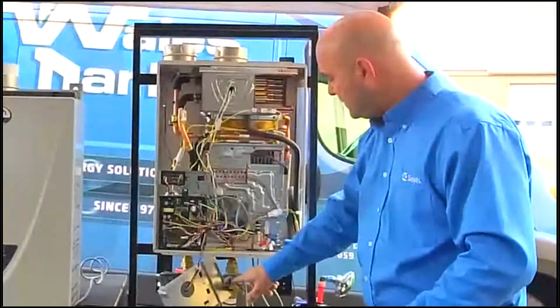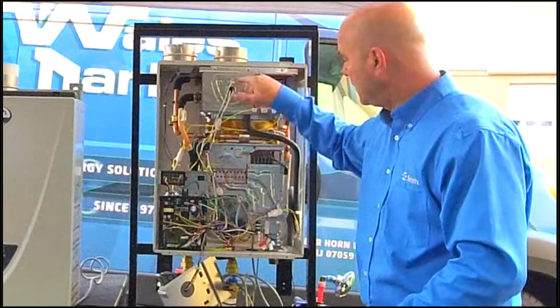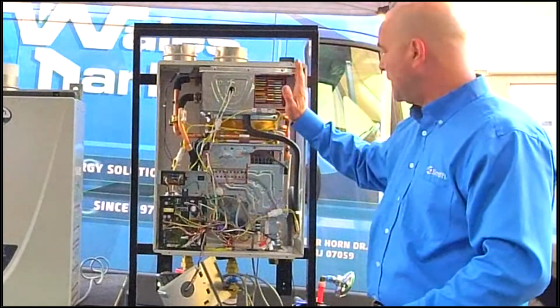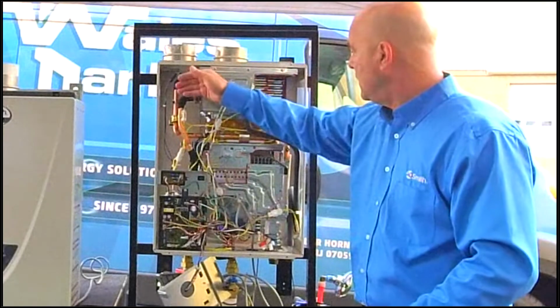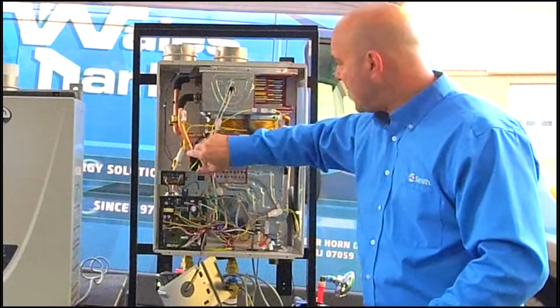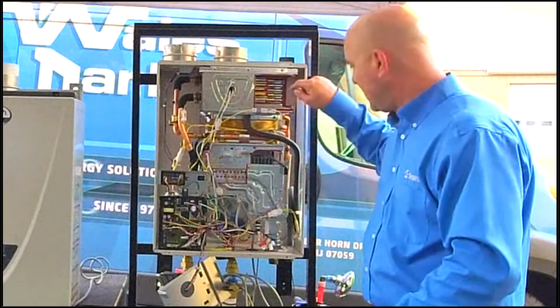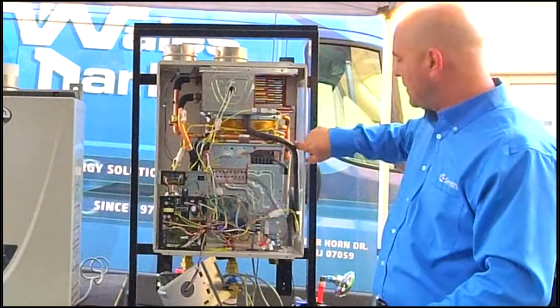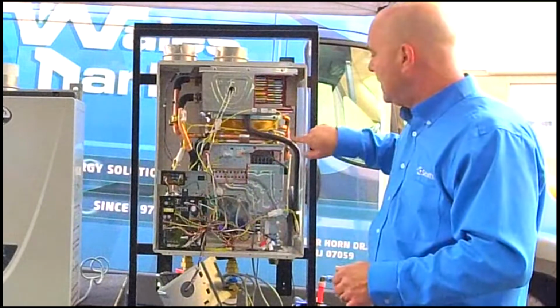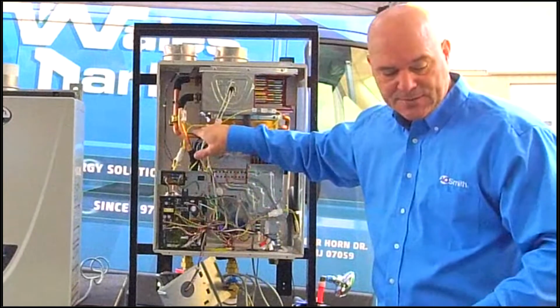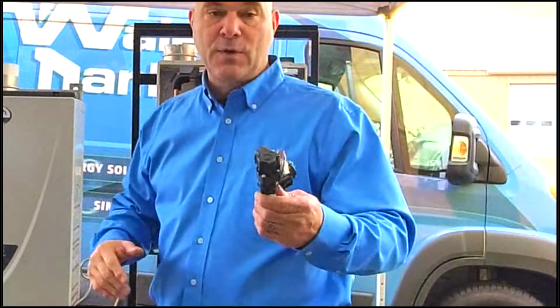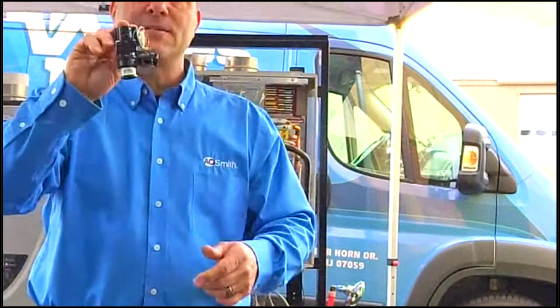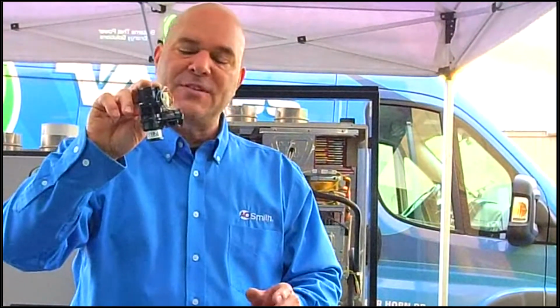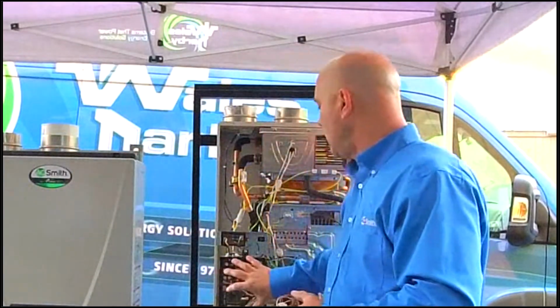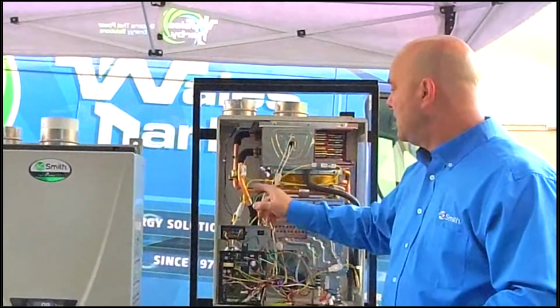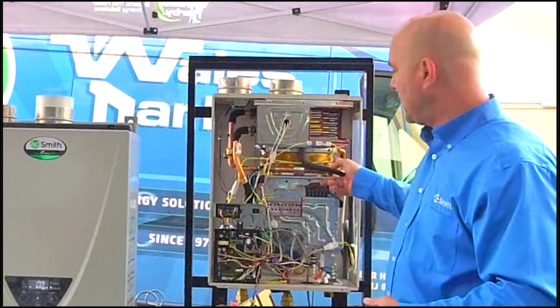So water pattern again, in the cold, up into the secondary heat exchanger first, comes over here to the end of the bulkhead, turns around, and goes back the other side of the bulkhead, comes down, around, and starts to wrap around the back of the heat exchanger. And we're taking the temperature right here with the thermistor as it's going through the heat exchanger, goes through this heat exchanger, comes out the other side hot. And on the 540 only, we have what's called a bypass valve. What that bypass valve is doing is it's getting a signal from the control. And the control is telling it based on some thermistor settings. You know, we're getting a thermistor reading here.